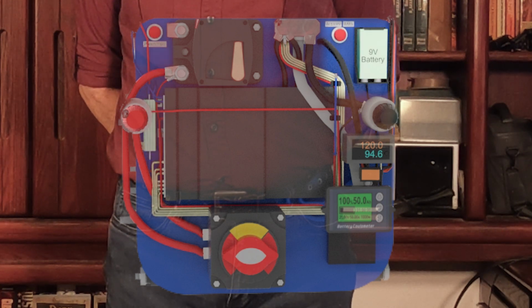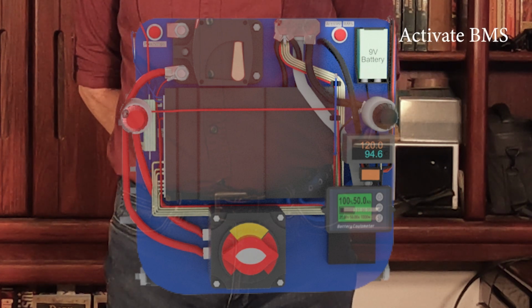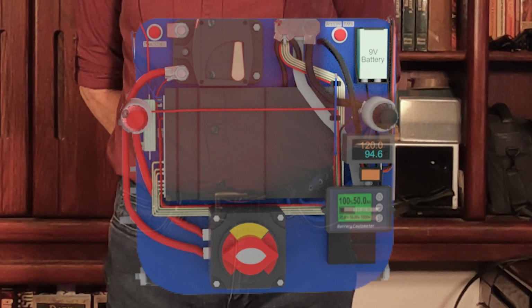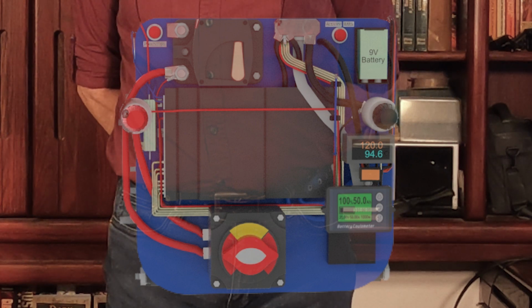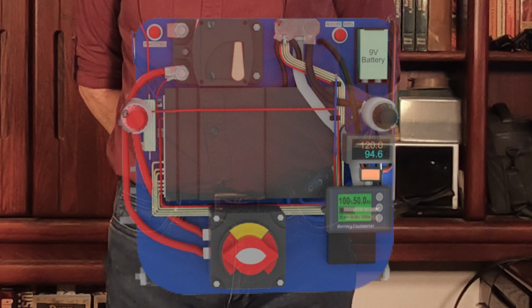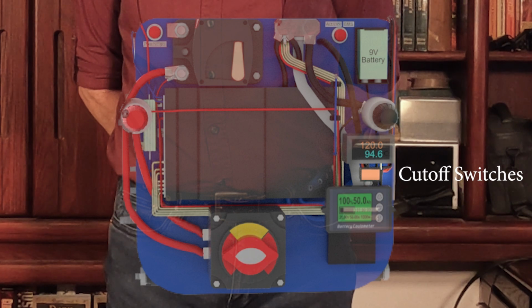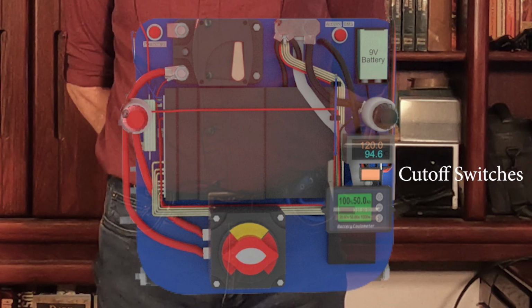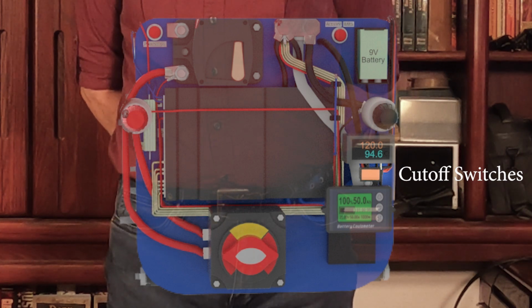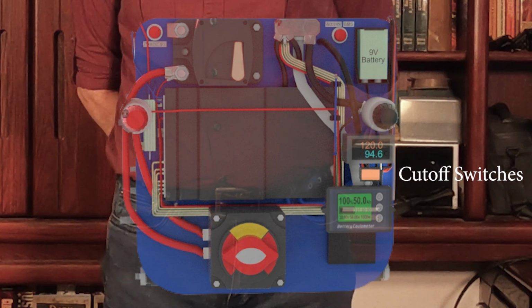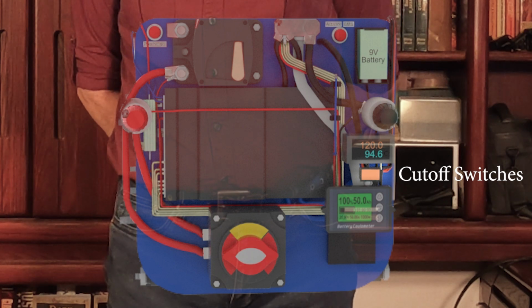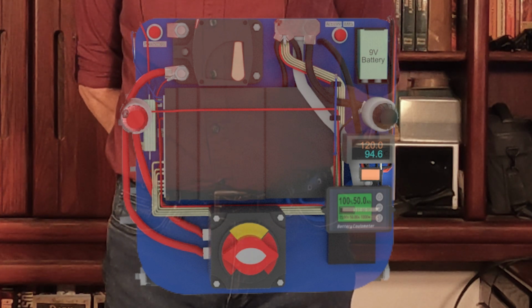Over here is the BMS activation circuit, which is used to start up the JK BMS when needed. There are two cutoff switches for the active cooling and heating circuits. These switches are mounted externally so that we can turn off those two systems anytime the batteries will be in storage or when these systems won't be needed, so they don't draw energy out of the batteries when we don't want them to be active.